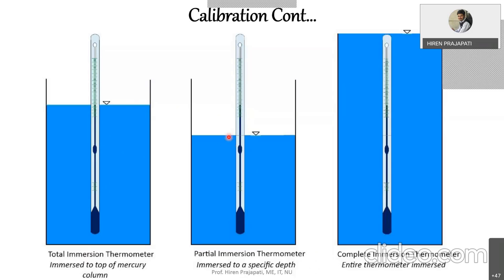For partial immersion, there is a reference line marked on the thermometer. When calibrating, the thermometer was kept inserted up to that reference line in the reference medium. Whenever you use this thermometer, you need to dip it up to that marking. Complete immersion means the entire glass stem up to the expansion chamber must be submerged within the medium for temperature measurement.